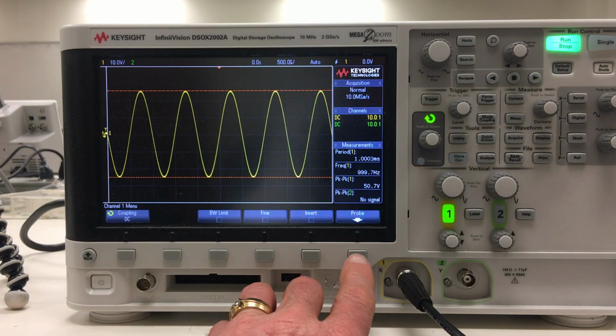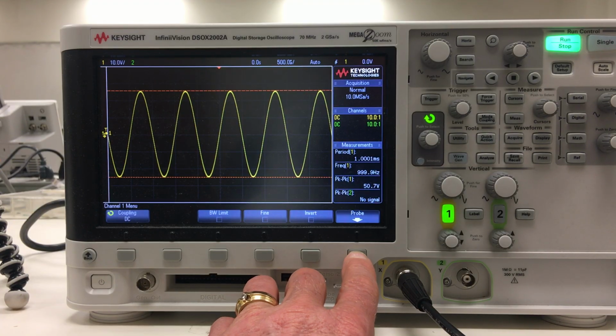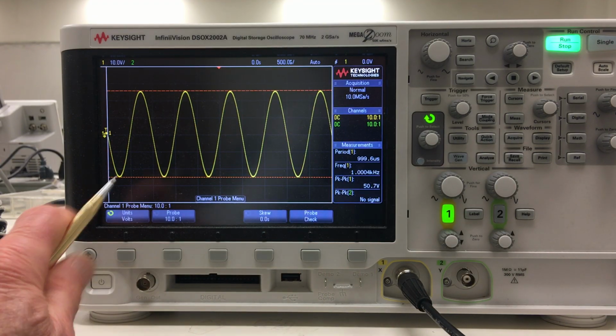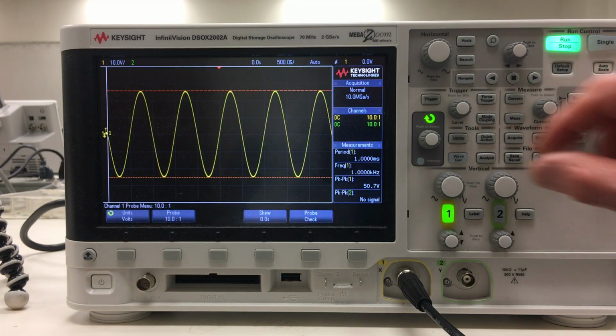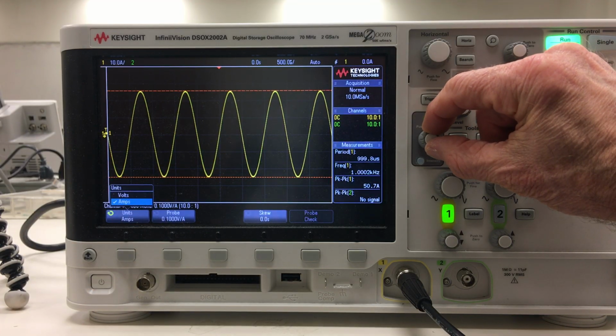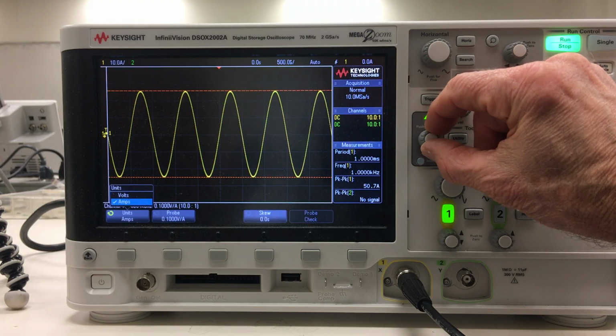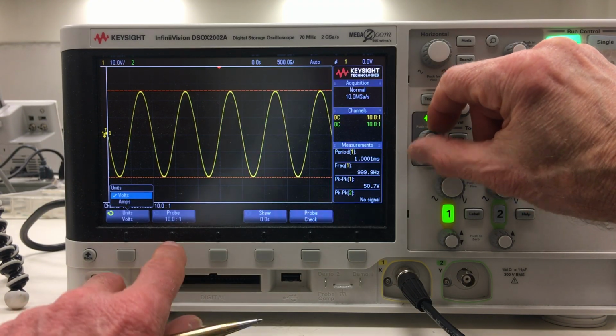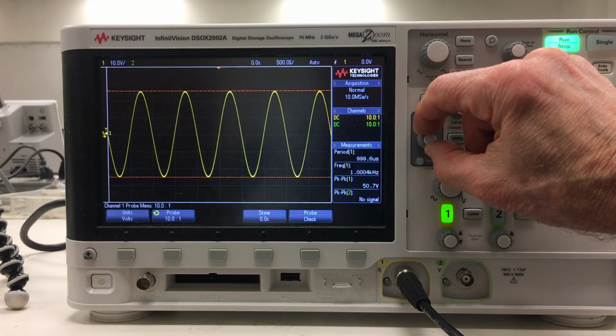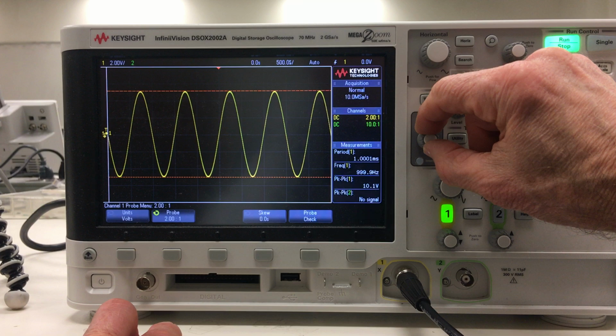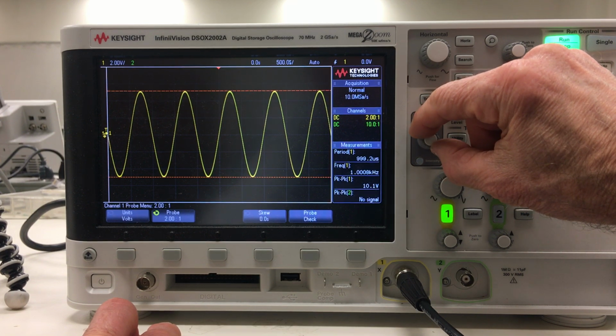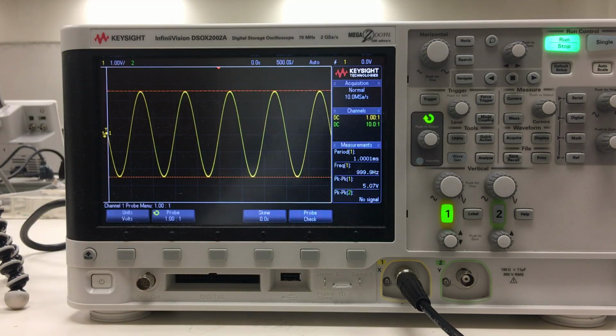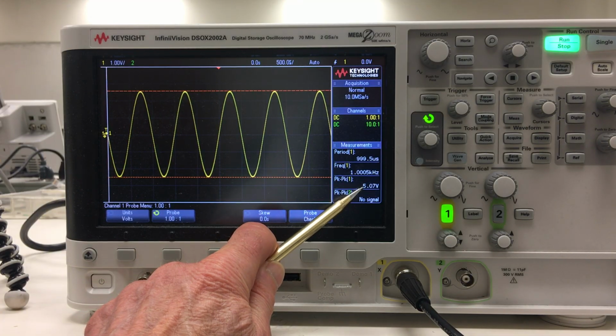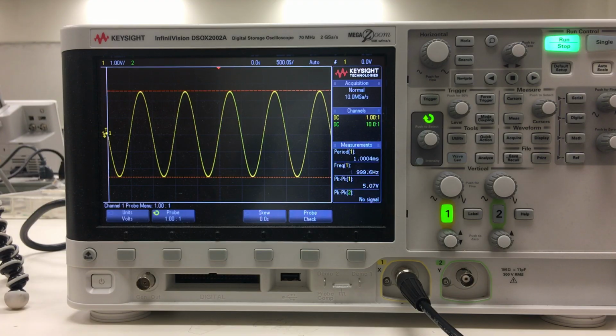Well, right underneath there is one of the soft buttons that says probe. So you hit the probe button, and now you look over here and it says 10 to 1. You can use the knob now to change that value. I'll go the right way here. Okay, I have 5 to 1, 2 to 1, and 1 to 1. So now our peak-to-peak voltage is 5.07 volts, the way it should be.